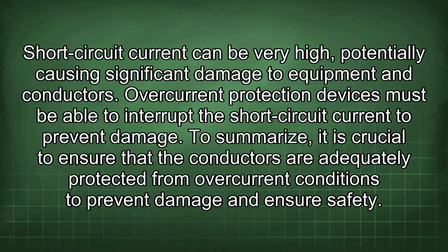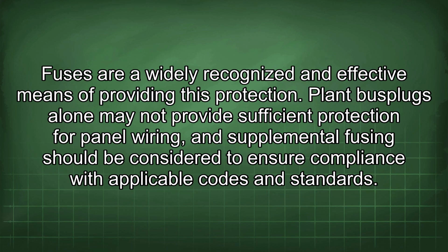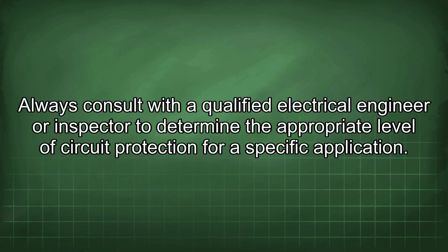To summarize, it is crucial to ensure that the conductors are adequately protected from overcurrent conditions to prevent damage and ensure safety. Fuses are a widely recognized and effective means of providing this protection. Plant bus plugs alone may not provide sufficient protection for panel wiring, and supplemental fusing should be considered to ensure compliance with applicable codes and standards. Always consult with a qualified electrical engineer or inspector to determine the appropriate level of circuit protection for a specific application.